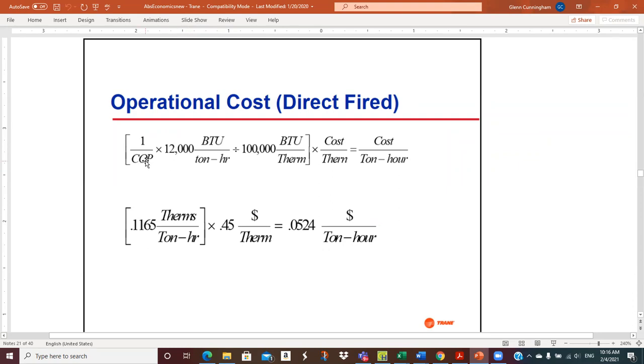Coefficient of performance is desired output divided by costly input. So this is output over input. When we divide, the outputs cancel and we get the costly input in terms of BTUs. And then how are we buying this energy? Well, we're basing it on 45 cents a therm. So we have to convert those BTUs to therms, and that conversion is divided by 100,000.